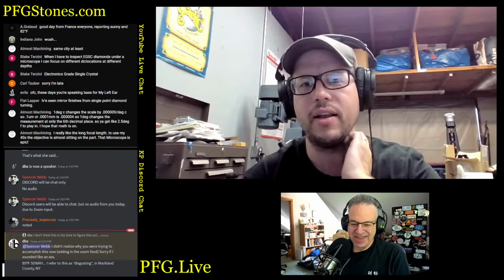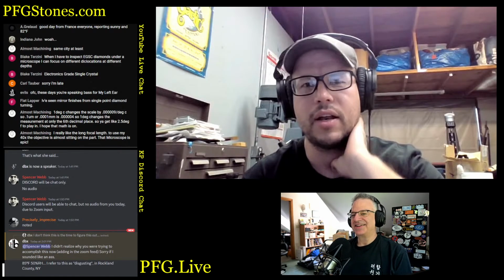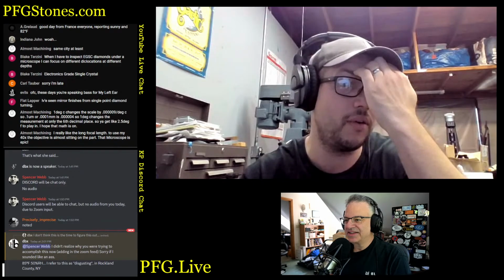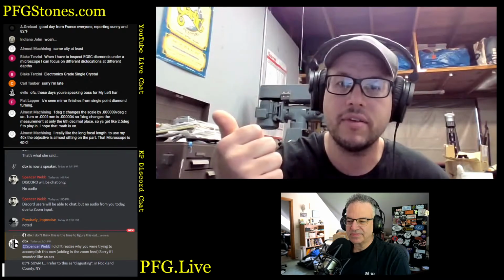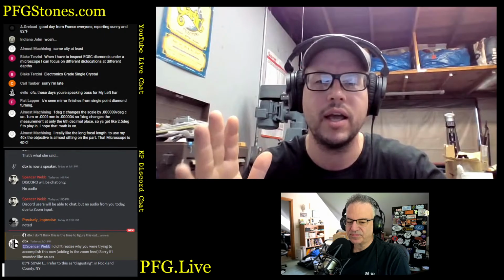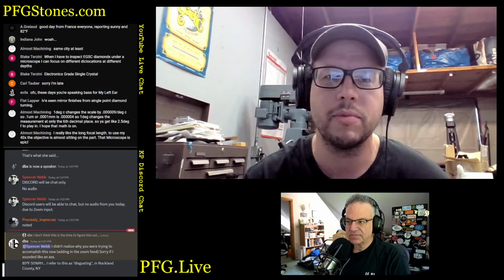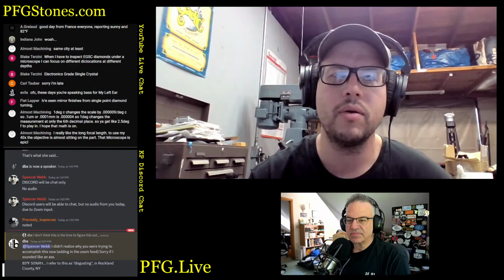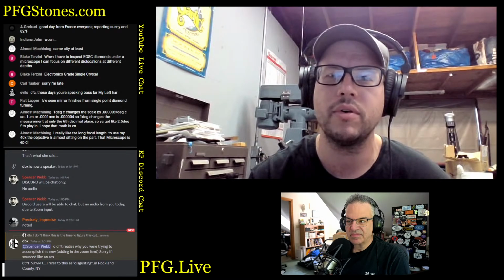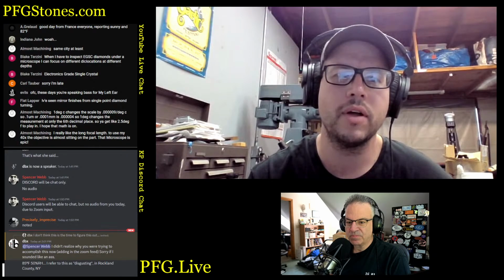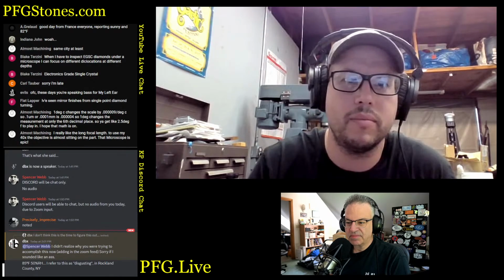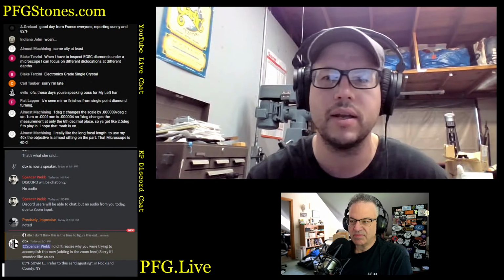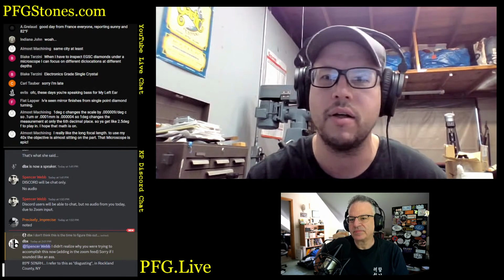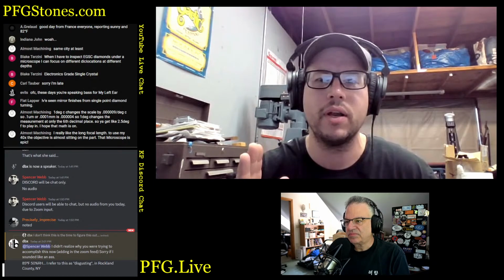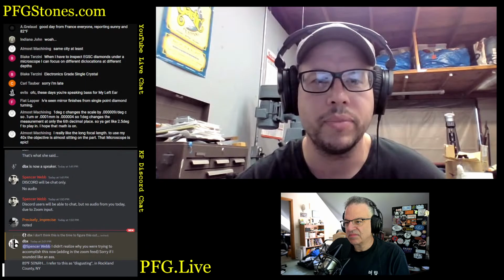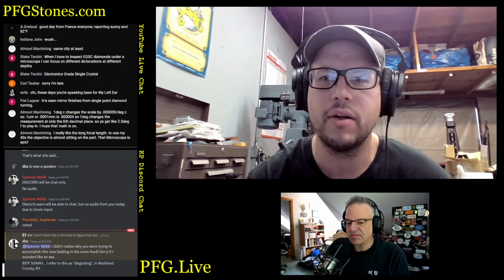Yeah, it's not like a huge. I guess it's not. It depends on the distance over which you're measuring, right? Right. So it's always the size of the temperature variation, the distance over which you're measuring, and of course the coefficient of thermal expansion of the specific material. So small changes around room temperature, over a small area, like when we're just measuring the diameter of a microscopic hole, it's actually not really going to factor in all that much. But if we're measuring over like a 4-inch envelope, then it could factor in. But again, like he was saying, they're pretty small values.